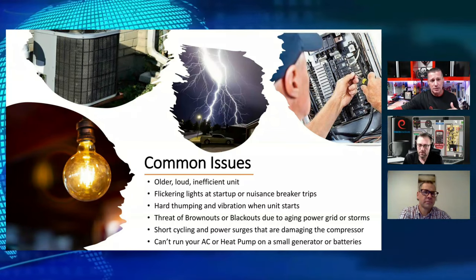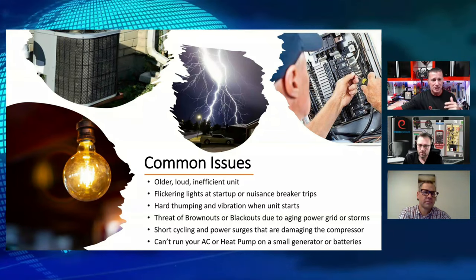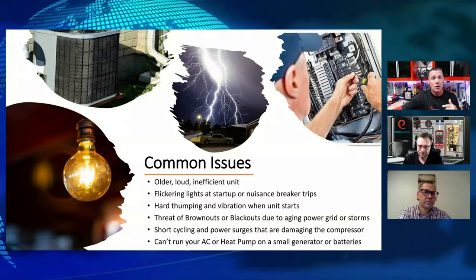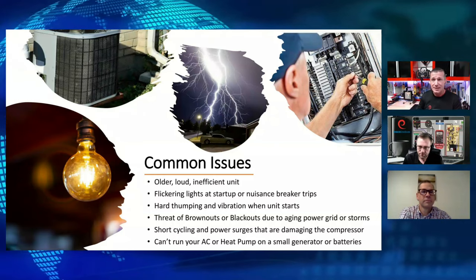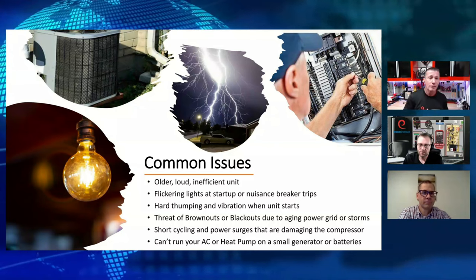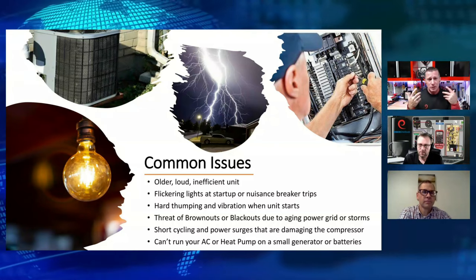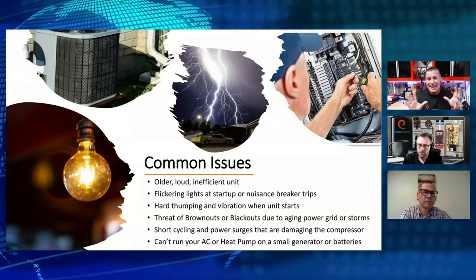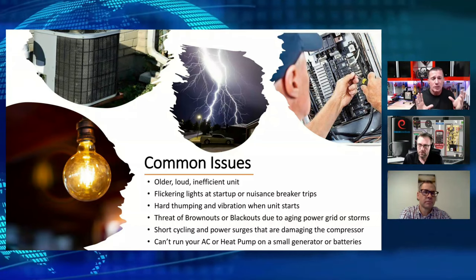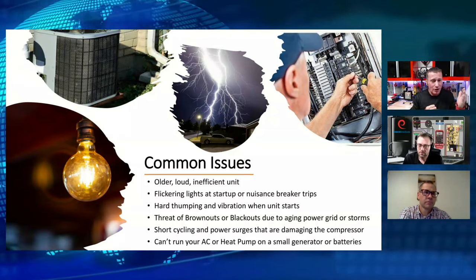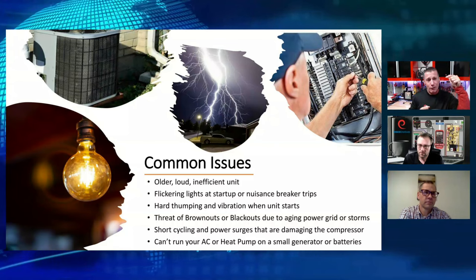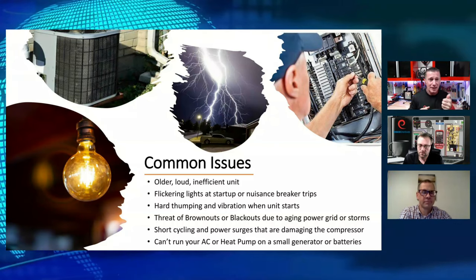We were looking to prove that we had a voltage issue going to the unit. So we installed one of the ICMs we talked about a few weeks ago, and we did some monitoring. We also added a data logger to that, and put the ICM on it to protect it from overcurrent, because our suspicion was that our voltage was dropping so significantly that our current was going up.